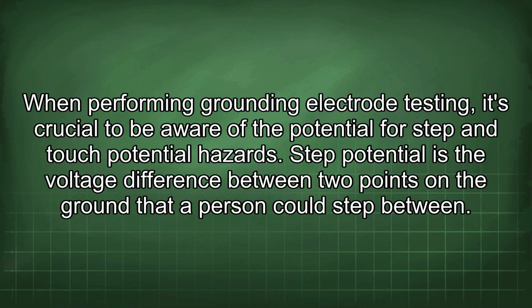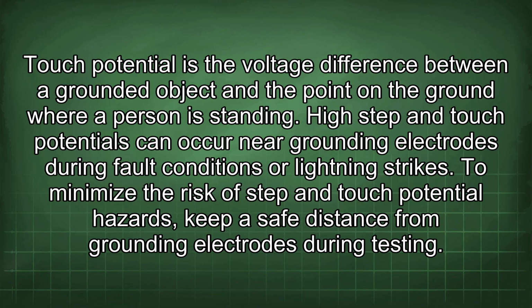When performing grounding electrode testing, it's crucial to be aware of the potential for step and touch potential hazards. Step potential is the voltage difference between 2 points on the ground that a person could step between. Touch potential is the voltage difference between a grounded object and the point on the ground where a person is standing. High step and touch potentials can occur near grounding electrodes during fault conditions or lightning strikes.